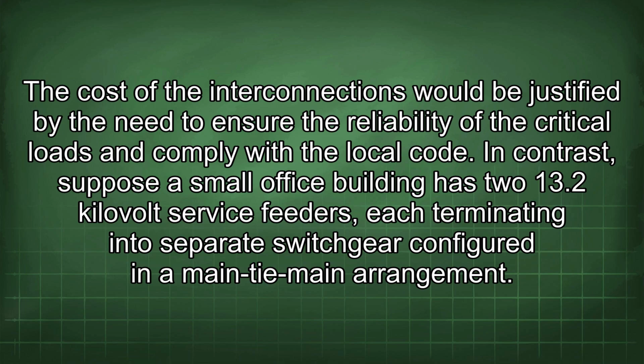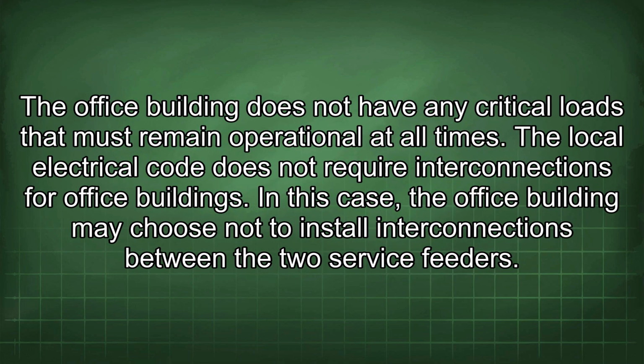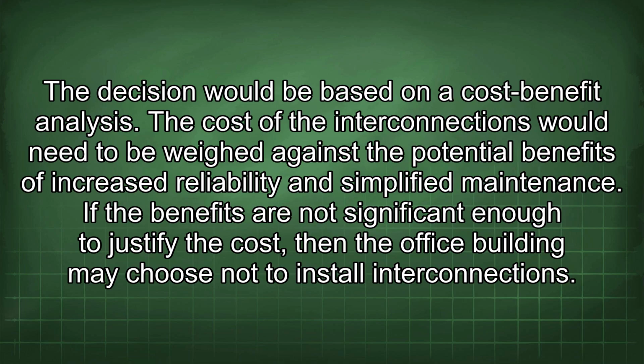In contrast, suppose a small office building has two 13.2 kilovolt service feeders, each terminating into separate switchgear configured in a main tie-main arrangement. The office building does not have any critical loads that must remain operational at all times. The local electrical code does not require interconnections for office buildings. In this case, the office building may choose not to install interconnections between the two service feeders. The decision would be based on a cost-benefit analysis.